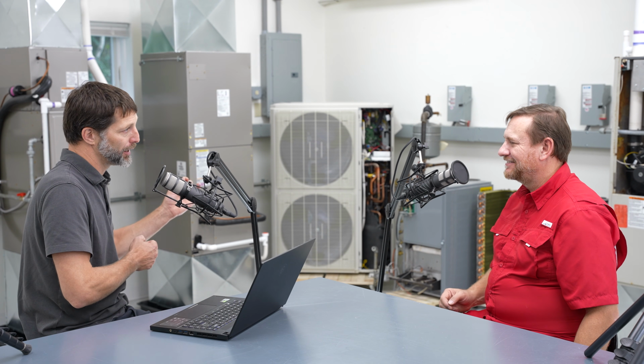It becomes a little dicey for newer technicians with the sequence of operation. The flame goes out and it just stops in the middle, say after 3 seconds, maybe if there's a flame rectification problem. Some newer technicians aren't aware you need to check for grounds and don't understand how the flame rectification process works, so they just go and blame the circuit board as being bad.